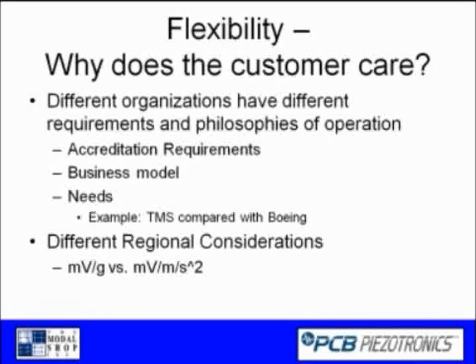We want accuracy too, but an annual calibration is probably more than what we need for rental inventory. A company like Boeing doesn't place as much value on calibration speed—instead they test every sensor before and after every test, comparing current results to previous results to make sure sensors are working properly.